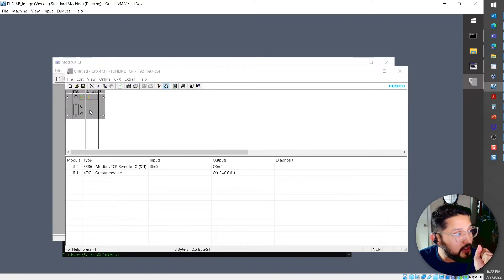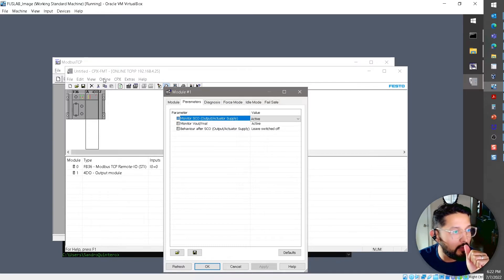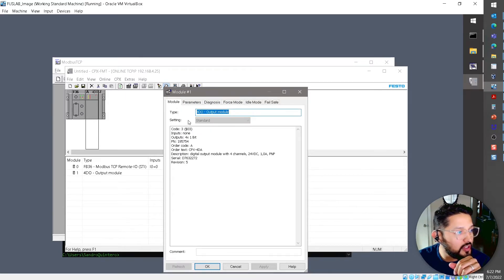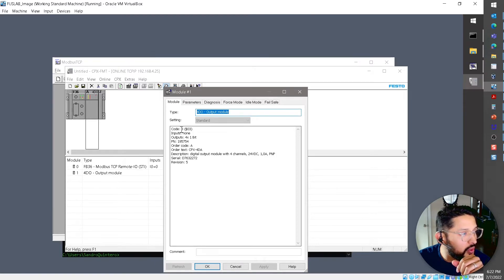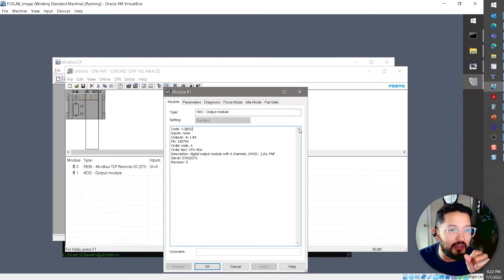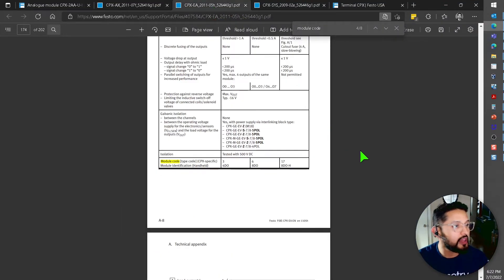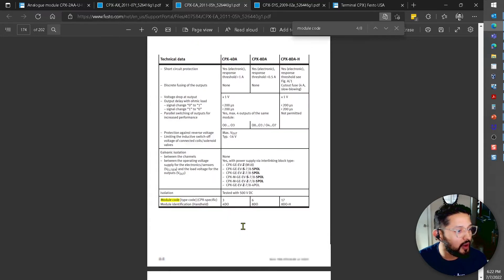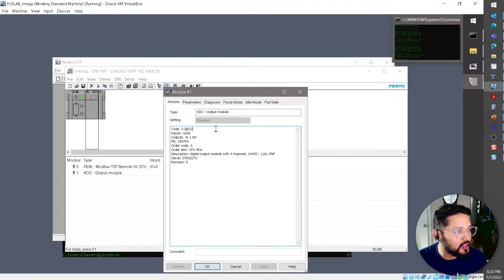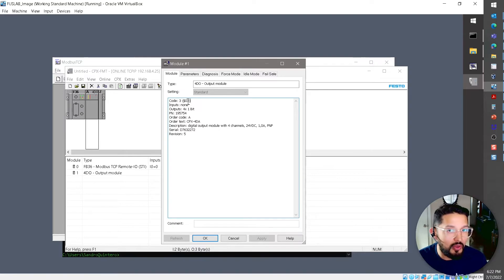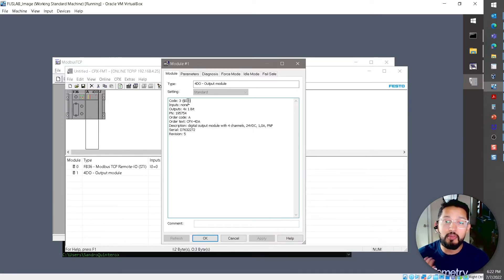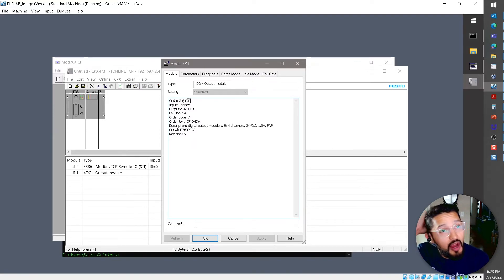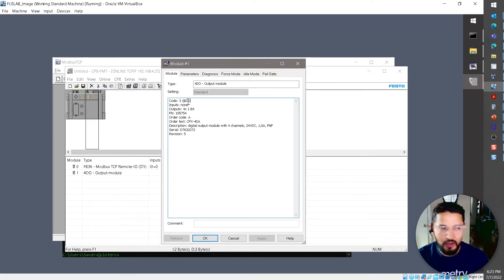Back after the swap. The CPX Maintenance Tool now shows 4DO — four digital output. If you double-click the module and go to the module tab, you can see code number 3. The user manual for the CPX four digital output module confirms module code 3. We can get this code programmatically via Modbus, which is the whole point — for example, to verify that the correct module is installed at each position in your PLC program.